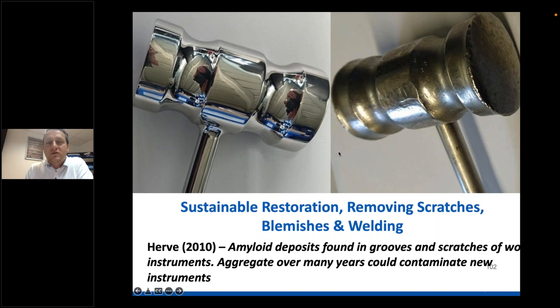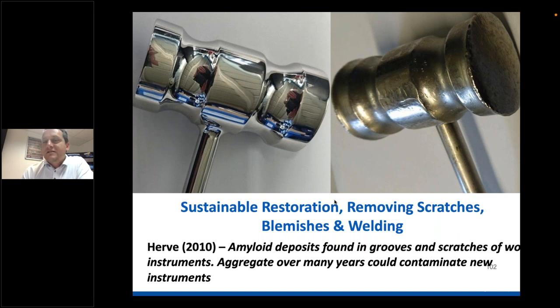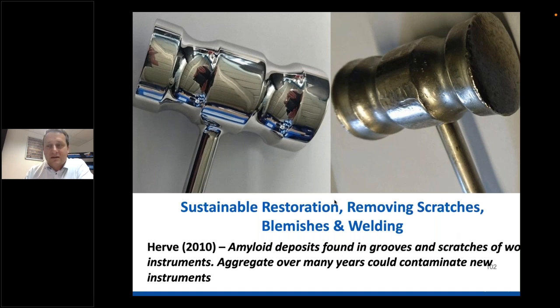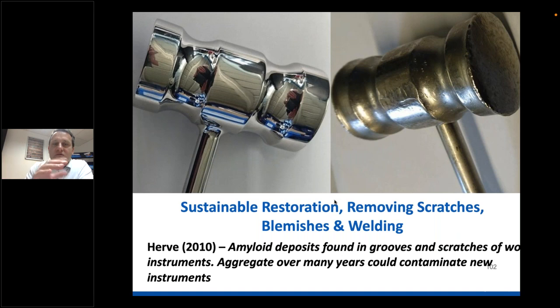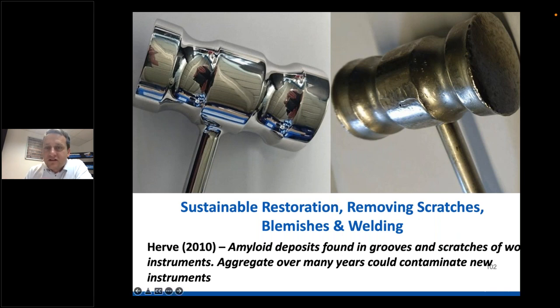Finally, repairs and refurbishment. Here is a before-and-after of a mallet we repaired - once you have the skills of a surgical instrument maker, you can refurbish devices, because if you know how to manufacture something you know how to repair it, and repair it to the required manufacturer's standard. Patient safety means we can't just repair things to a poor quality. A mallet can be re-ground, refinished - grinding the steel back to a very fine finish reduces surface area again, improving corrosion resistance and reducing protein adhesion. All very positive.